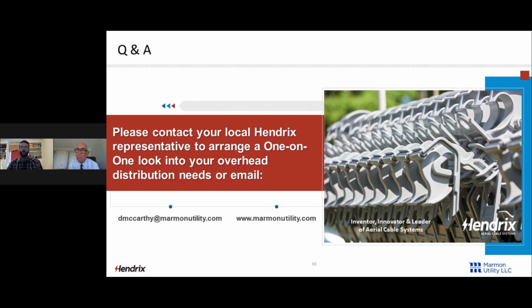Someone was wondering, has the spacer cable experienced a break? And if so, how was it repaired? Easy. Phase conductors on spacer cable do not break, because anything that hits them is going to hit the messenger, it's going to break the pole. The spacer cable does not break. However, has it ever broken? Yes. I mean, with 500,000 miles in 72 years, hopefully something has broken. Yes, it has broken.